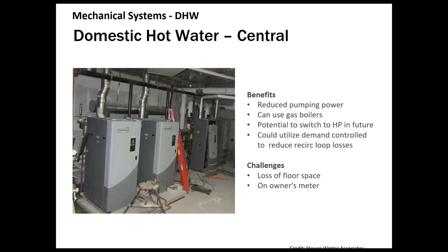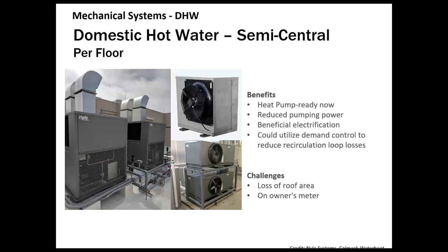In other words, it only turns on when there is demand. One of the challenges, of course, of the central systems is loss of floor space. And of course, again, it is on the owner's meter, and so not a tenant-based type system. Semi-central, as an alternative to that, is now available in the heat pump world, but could also be addressed on a natural gas basis. And it has many of the same benefits, including it can help migrate over towards beneficial electrification of buildings, and again, can use the demand control to help further reduce losses. These types of heat pump condensing systems do require roof area and similarly are on an owner's meter, but they are available and in the market now.